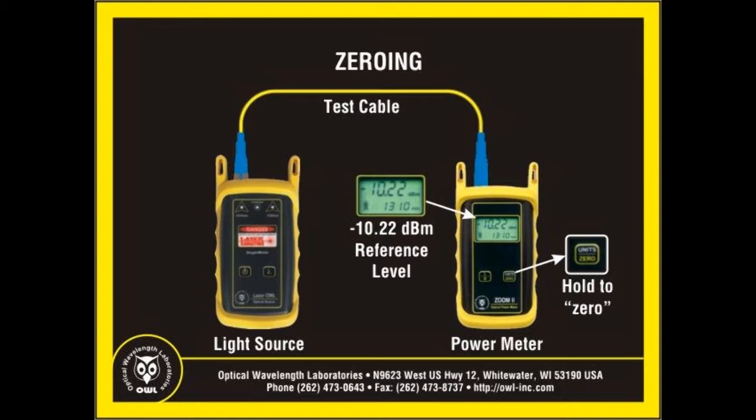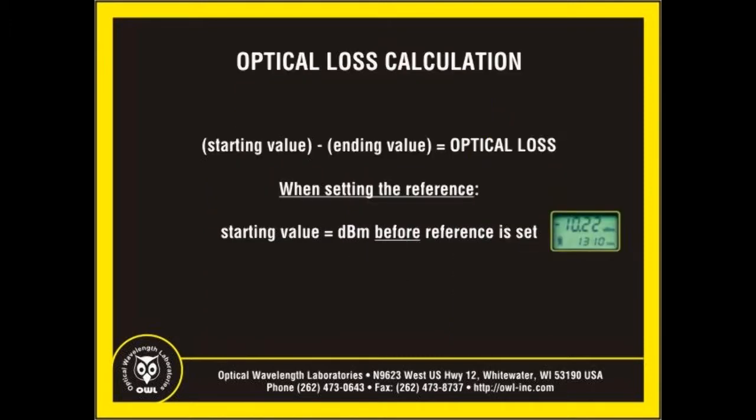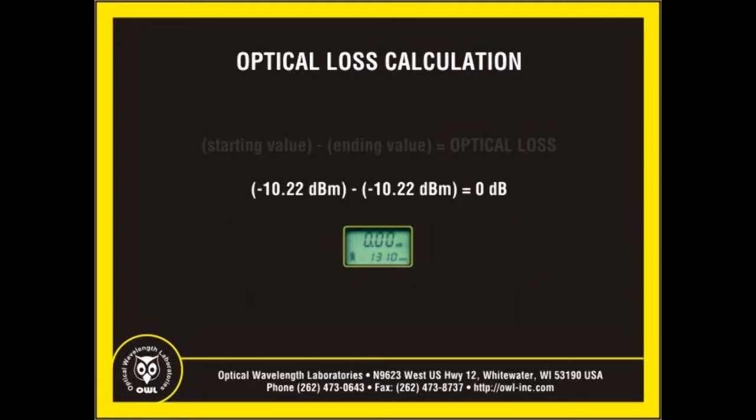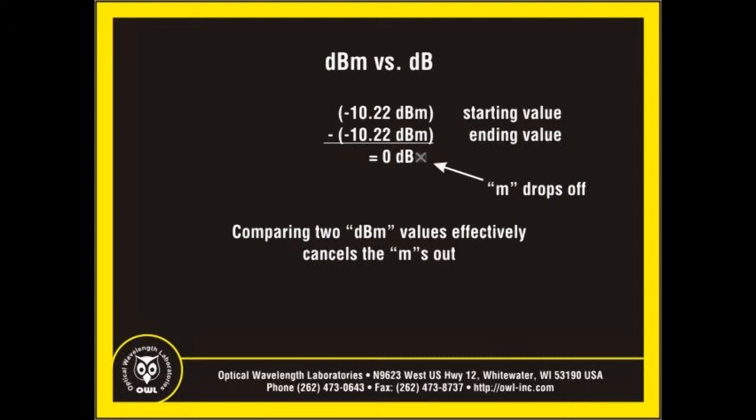Up until now, we have been dealing with optical power measurement, which is a measure of the actual brightness of a source. Carrying this concept over to optical loss measurement — which is the difference between two brightness measurements — the starting value is the output power of the test light source as measured through reference cables, and the ending value is the power measured through the link under test. Most optical power meters have a button or process by which the reference level is recorded internally. Comparing the reference level to itself results in a measurement of zero dB, which is the same as saying the power meter has been zeroed. Notice that the M has dropped off — you are no longer interested in the actual brightness of the source, but in the difference between values. When comparing two separate dBm values, the M drops off and you are left with a measurement unit called dB.